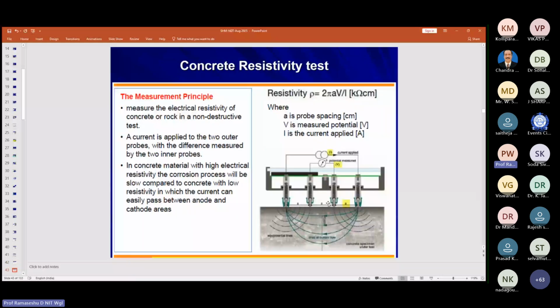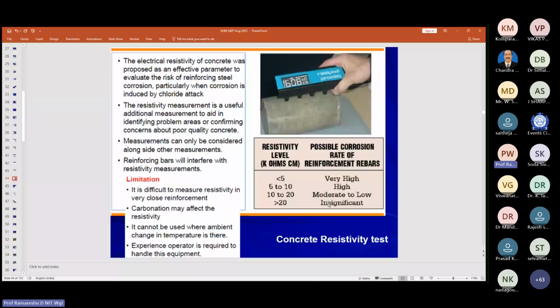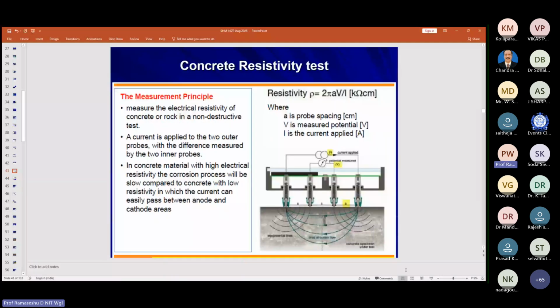Then another handheld instrument is a resistivity meter. A resistivity meter looks like this. It's a very small handheld instrument. It has four probes: two external probes and two internal, intermediate probes. One is the pulse generator, and another is the receiver line. In this resistivity meter, we measure the normal electrical resistivity of the system. Depending upon the electrical resistivity, one can assess the corrosion of the system.